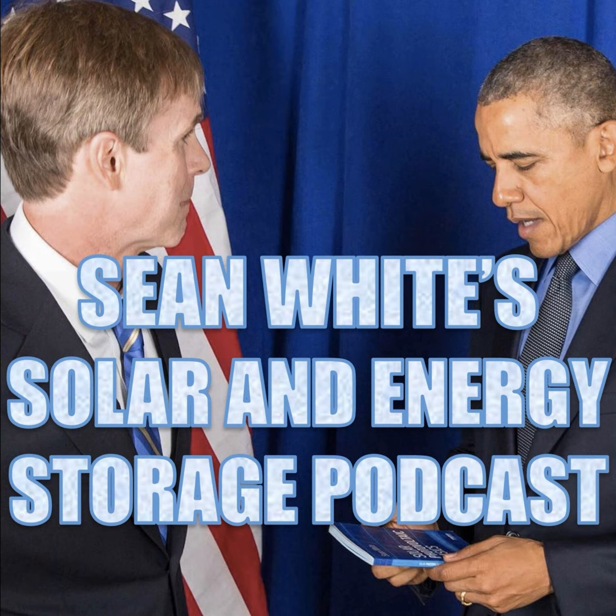And let's read what a microgrid system is. According to this definition in Article 705, it is a premises wiring system that has generation, energy storage, and loads, or any combination thereof that includes the ability to disconnect from and parallel with the primary source. One of the things that people get a little bit confused about, and one of the reasons why this is probably going to be changed, is you can have a mountaintop microgrid system. That means that it will never connect to the grid. So that would be its own microgrid system without a grid connection.